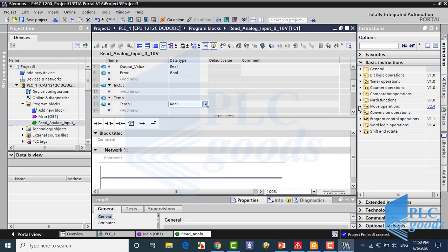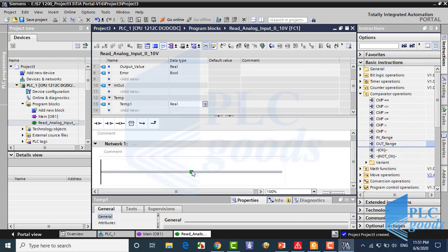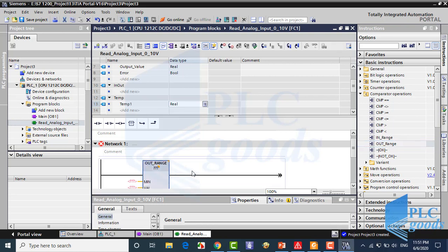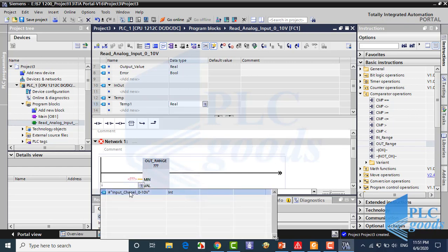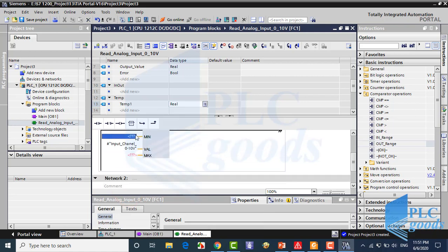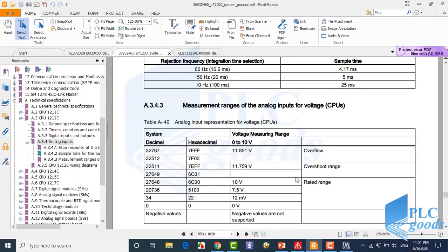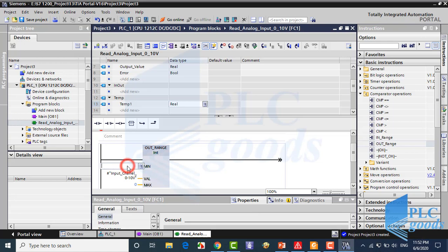Okay, in the first network, I'm going to use the outrange instruction to activate the error output. If the input measurement is not between 0 and 27648, the error output will be on, because the measurement value is not in its rated range.